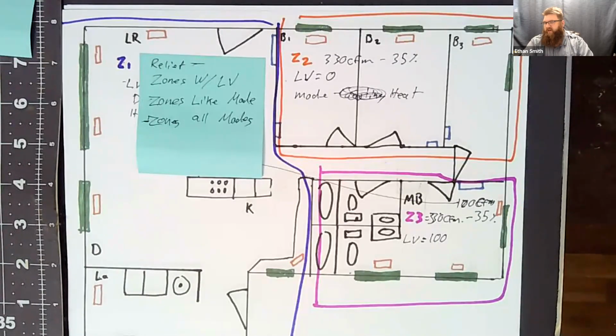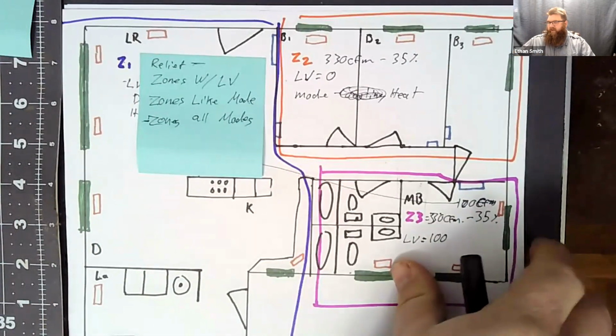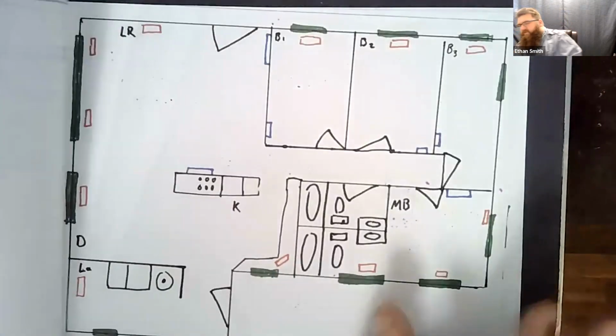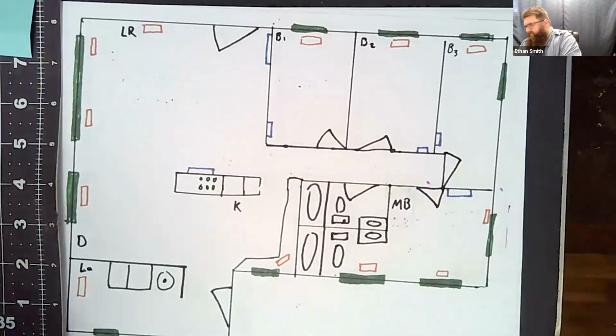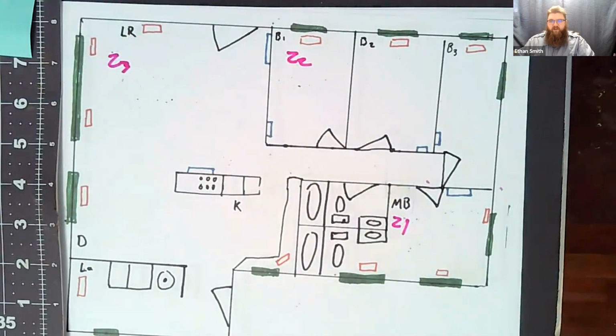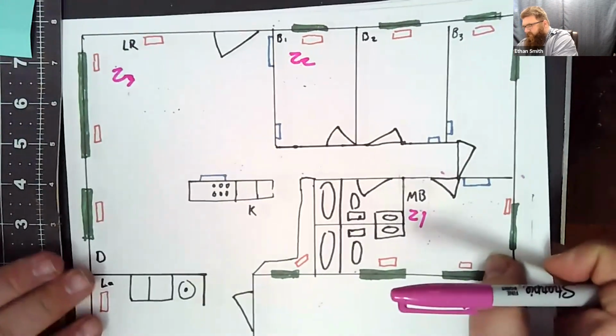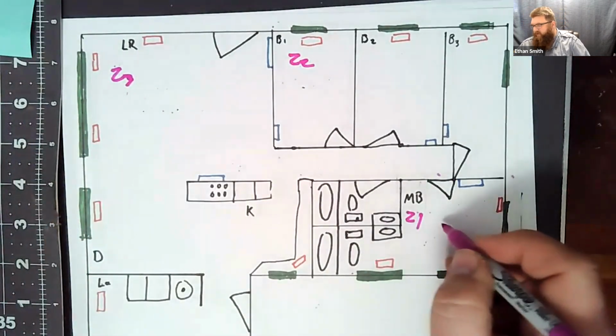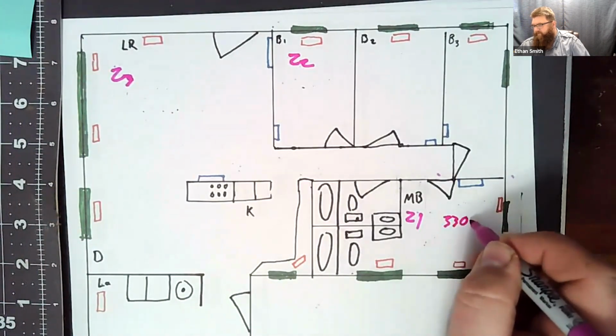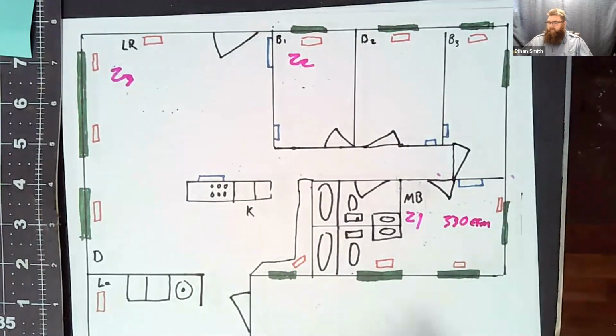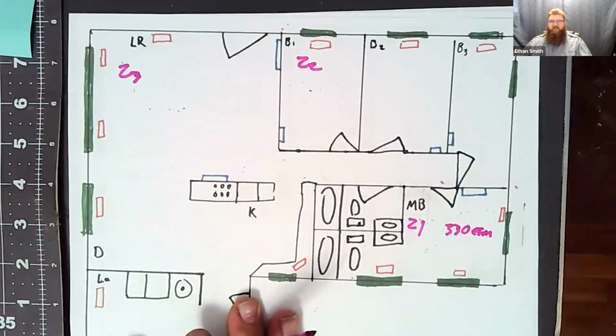It allows you to manage that excess air without neutering your equipment, lets you manage that excess air without costing the homeowner extra money. So where this really comes into play, guys, and where we can really manage our relief really well is I can take that same zoning system and if I put a variable speed outdoor unit and or a modulating furnace on this thing, I can match anything that happens. So if my zone 1 over here needs 330 CFM, my 3-ton AC that I've got on that has a 25% turn down.